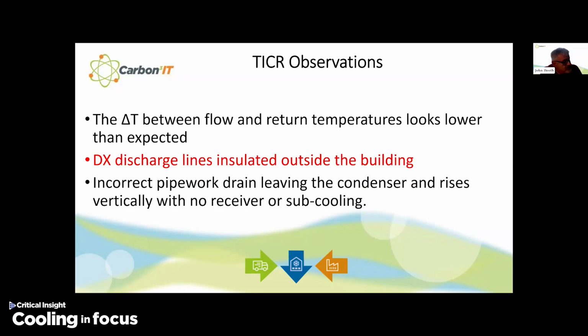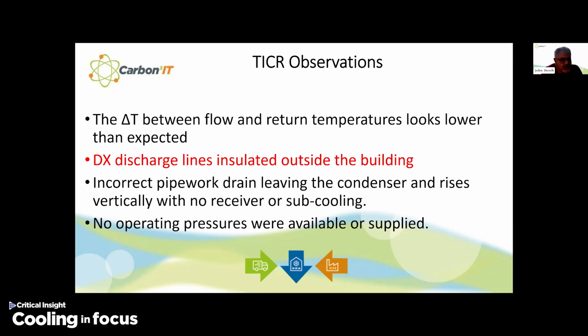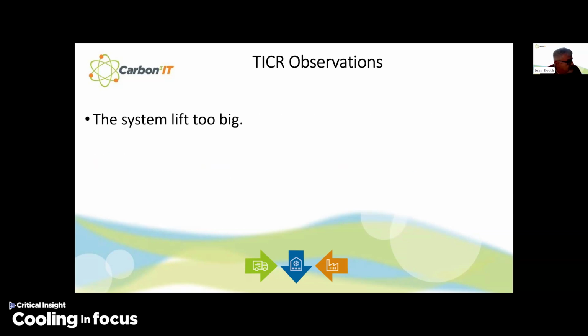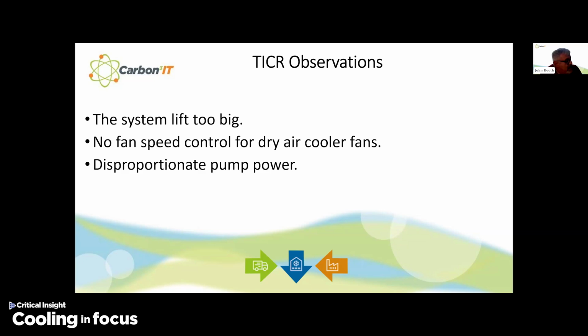We found incorrect pipework drains, leaving the condenser and risers vertically with no receiver or subcooling. This is where basically you're using more energy to get your fluid around the system. And in the service records, we found no operating pressures were available or supplied by the manufacturers or the service company. We found the system lifts were too big. We found no fan speed control for dry air coolers. We found disproportionate pump power. AC motors with forward curved belt driven fans, basically they're always on, so they should be EC fans, which is a code of conduct best practice.